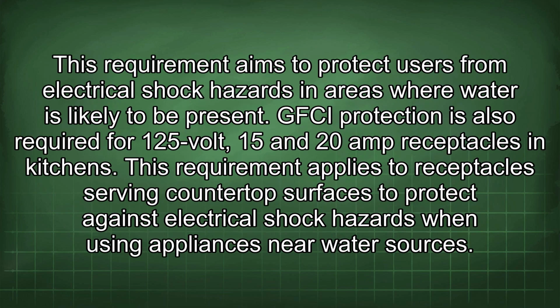This requirement aims to protect users from electrical shock hazards in areas where water is likely to be present. GFCI protection is also required for 125 volt, 15 and 20 amp receptacles in kitchens. This requirement applies to receptacles serving countertop surfaces to protect against electrical shock hazards when using appliances near water sources.